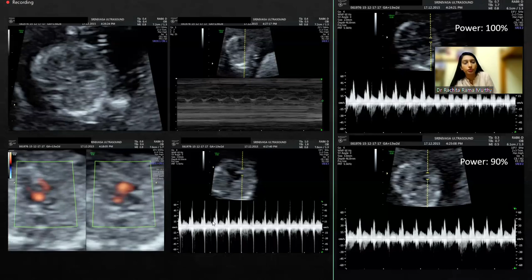Watch the TI and MI on your screens. On the top of your screens, usually the MI and TI indices are denoted over here. TIS is thermal index soft tissue, TIB is thermal index bone, and then the mechanical index. All of these parameters should be visible on your screen for any scan, and all of these should be less than 1. That is the allowed limit for any ultrasound scan. ALARA principle, as low as reasonably allowable. So please keep these indices less than 1. If you're seeing that it's going above 1, reduce your power and adjust your other settings.